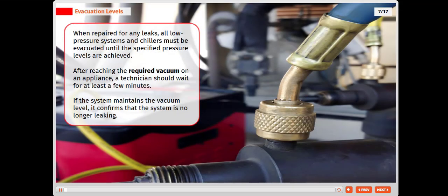When repaired for any leaks, all low-pressure systems and chillers must be evacuated until the specified pressure levels are achieved. After reaching the required vacuum on an appliance, a technician should wait for at least a few minutes. If the system maintains the vacuum level, it confirms that the system is no longer leaking.